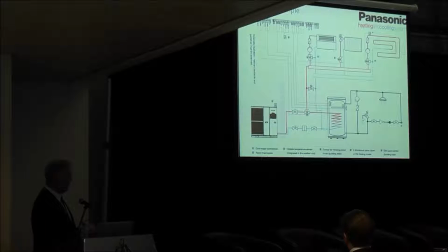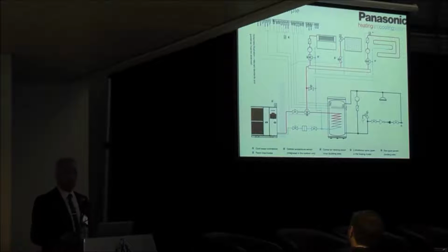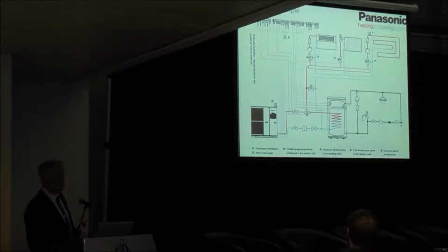Once the hot water demand is satisfied, there's a sensor in here. It switches the heat pump into the heating mode, which switches the three-way valve and diverts the water flow into the heating circuit. The heating circuit can be underfloor, low temperature radiators, standard radiators, or fan coils. It's just a heat emitter. The engineer decides, the architect decides, the customer decides what the heat emitter is. The set point for the heating side depends on your heating emitter. If you have low temperature radiators, you can have 45 degrees. Standard radiators can be 55 to 65 degrees, on the floor 35. It just does depend on the heating emitter.